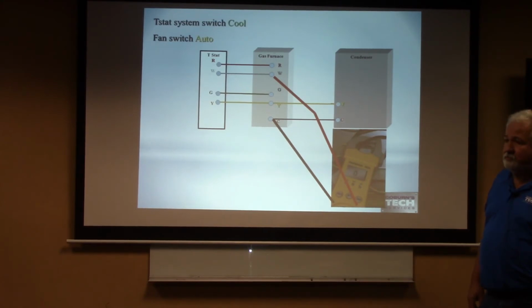0 volts, because I'm seeing nothing from the red going to the W. Is that right? Correct. Good. What would I see on the G? Am I going to get the fan relay to kick in on this? Good. I have to energize that G, so I would see 24 volts there. What would I see on the R and the C in the heating mode? Okay. Sure enough, there it is.